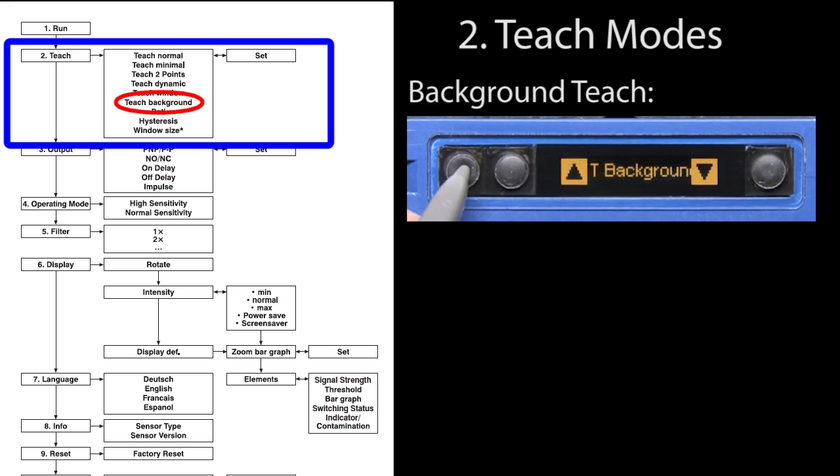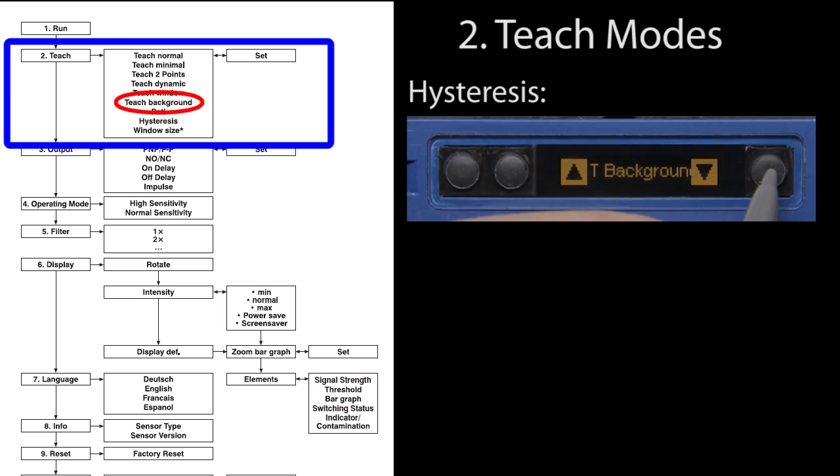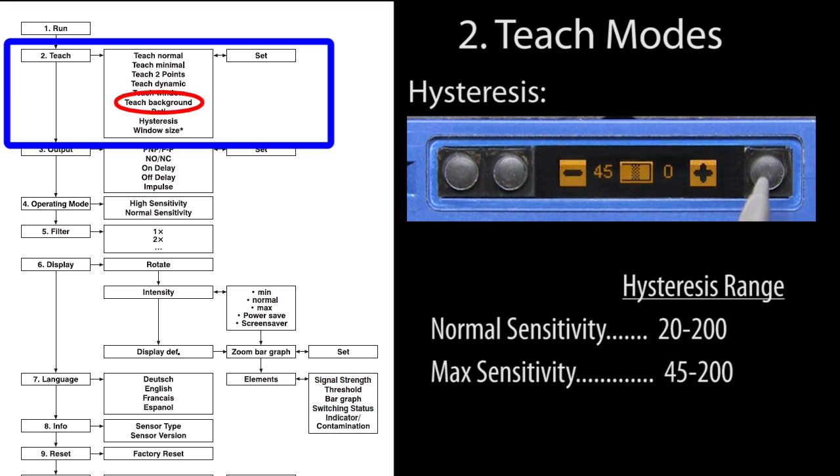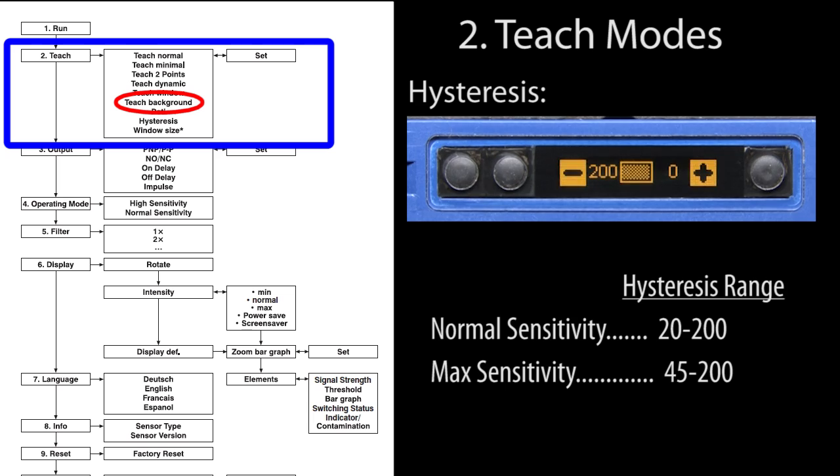The final teach mode is background. Just point the sensor at the background and hit the T key. The sensor automatically sets the threshold just above the background. There is also a hysteresis setting that you can adjust just like all the others. The only catch is the amount of hysteresis you can use depends on the sensitivity setting you set for the sensor. This sensor is on high sensitivity so I can only select a hysteresis of 45 to 200. On normal sensitivity you can change hysteresis from 20 to 200.